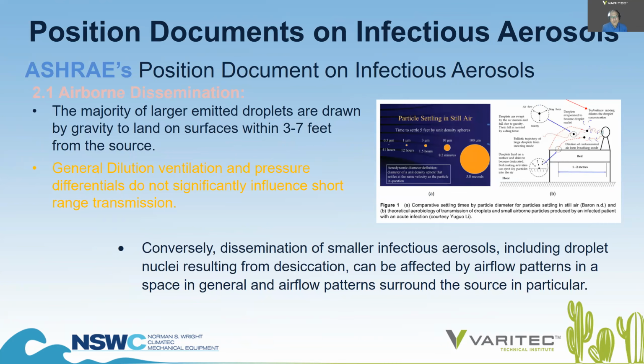ASHRAE goes on to say the majority of larger emitted droplets are drawn by gravity to land on surfaces within 3 to 7 feet from the source. And that falls right in line with the CDC 6-foot social distancing guideline. It works. ASHRAE goes on to say general dilution ventilation and pressure differentials do not significantly influence short-range transmission. In other words, particles of 100 microns are going to precipitate out, and there's nothing you can do with the HVAC system that's going to impact or mitigate the risk of transmission from that source within the 6-foot social distancing guidelines.